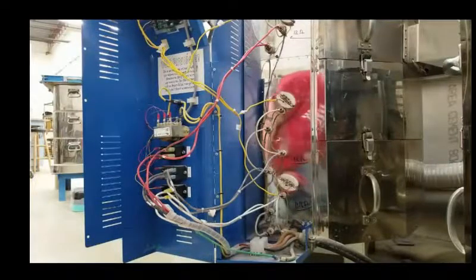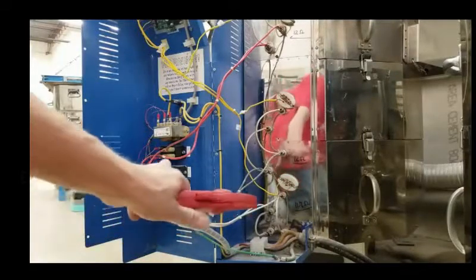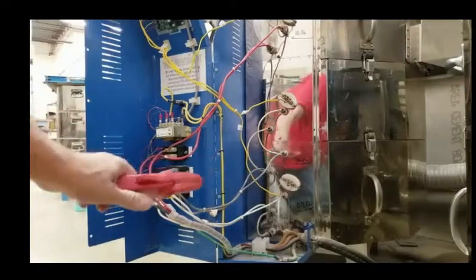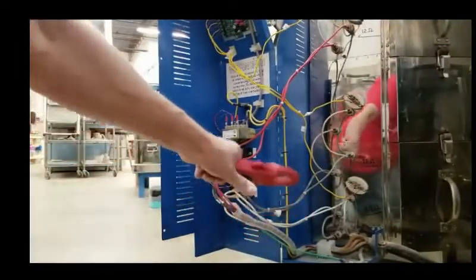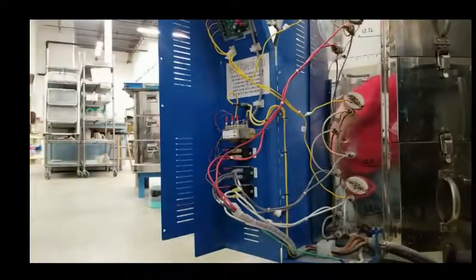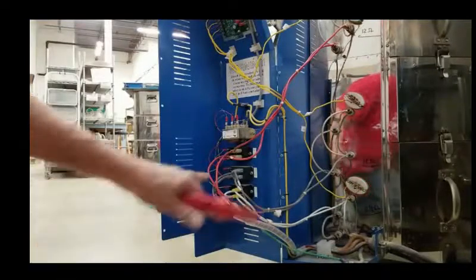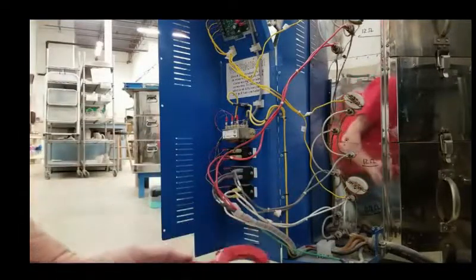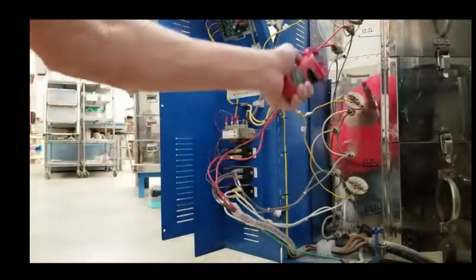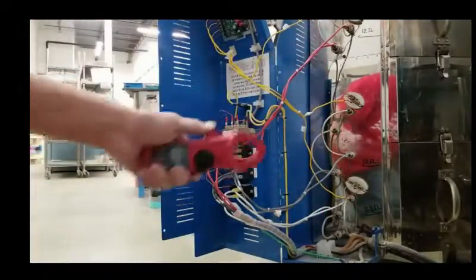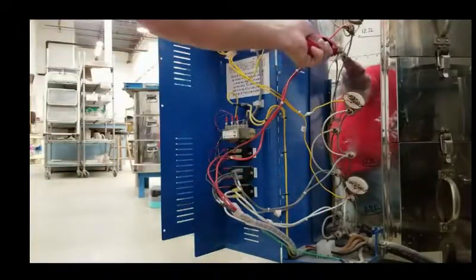We're going to go a step further. We're going to let this run until it reaches a few hundred degrees, and these relays have been running. So one of the questions is, how do we check these relays? Well, if one of these relays was bad, we would get no reading. So let's say the top relay was bad, we'd put our amp probe here, we'd get nothing.